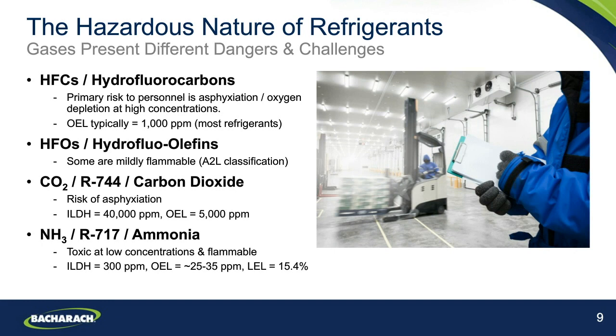Ammonia, of course, is broadly used in industrial refrigeration applications, and ammonia presents a unique set of dangers compared to the other refrigerants typically used because it is toxic at fairly low concentrations, with an exposure limit typically in the region of about 25 to 35 parts per million. We do see variances in different geographies within that kind of range, but it is typically that low level that we're looking at a risk being identified. There is an immediate danger to health at 300 parts per million, which we can see is much lower than for the other refrigerants out there. And of course, with ammonia, there's also a flammability risk, with ammonia having a lower explosive limit of 15.4% by volume. So a large leak, of course, goes beyond that toxic risk and becomes a flammable explosion hazard as well.